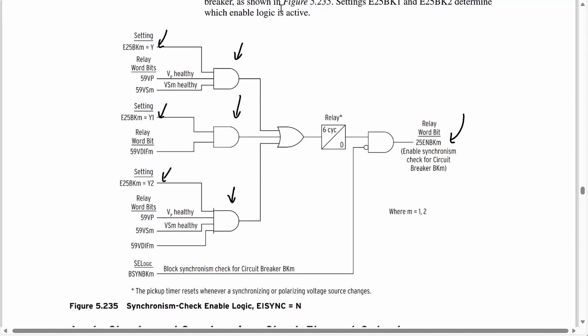So in this case, 59VP1 signifies that the voltage VP, which is the line side voltage in our case, is within a healthy window. And then we have the sync voltage 59VS1, which is going to be the bus side voltage for breaker number 1. So those two, as you can see over here, have to be within a healthy window. And we're going to see here in a second how we define that healthy window.